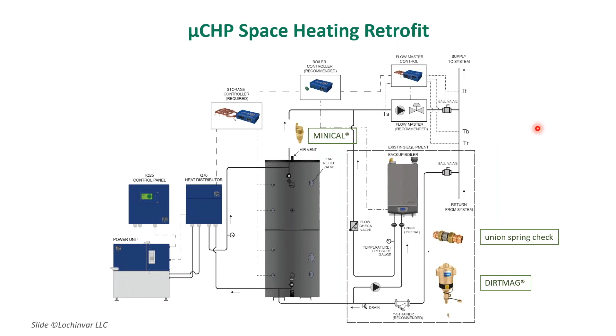As I mentioned earlier, with the 6-unit job in Canada, we do have applications with multiple units. And again, this is where the centralized and decentralized story comes in. We can put a couple of units together, or you can put single units together. The important thing to remember in applications is that the cogens are hooked parallel. The storage tanks are connected in series. The reason it's connected in series is because we need a delineated stratification point somewhere in these two tanks. If we did it parallel, what would happen? The tanks would go down evenly, and it would confuse the sensors' understanding of where the delineation for the stratification is. So series on the tanks and parallel on the cogens.